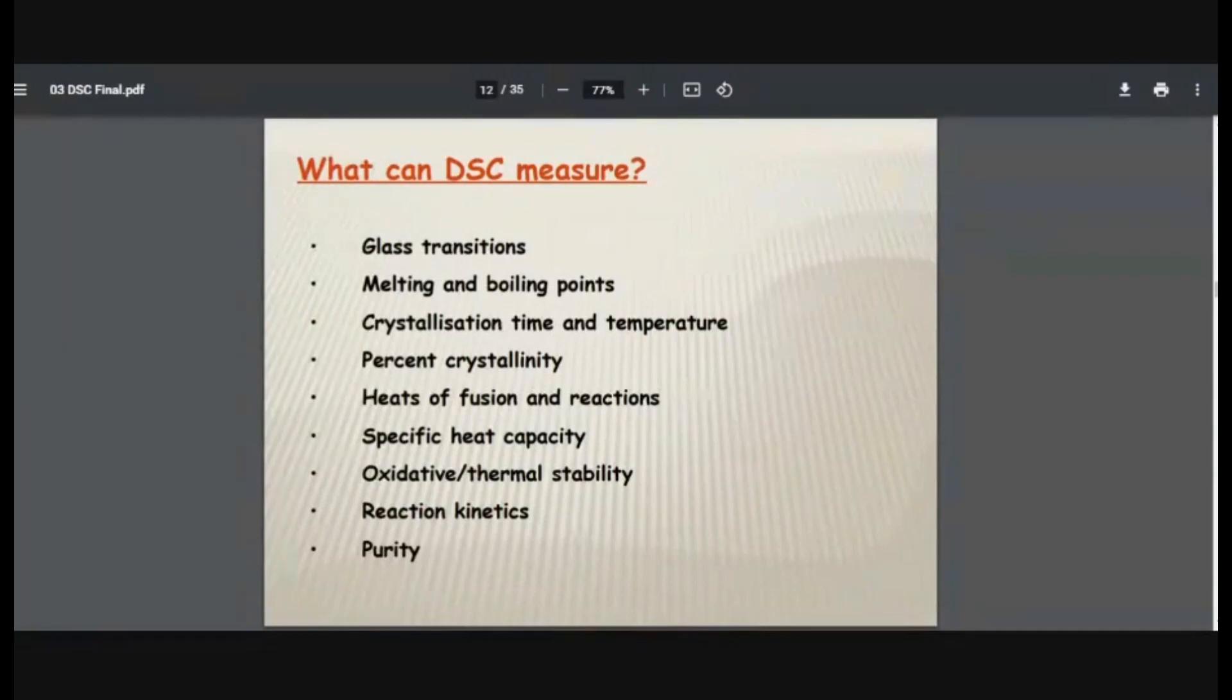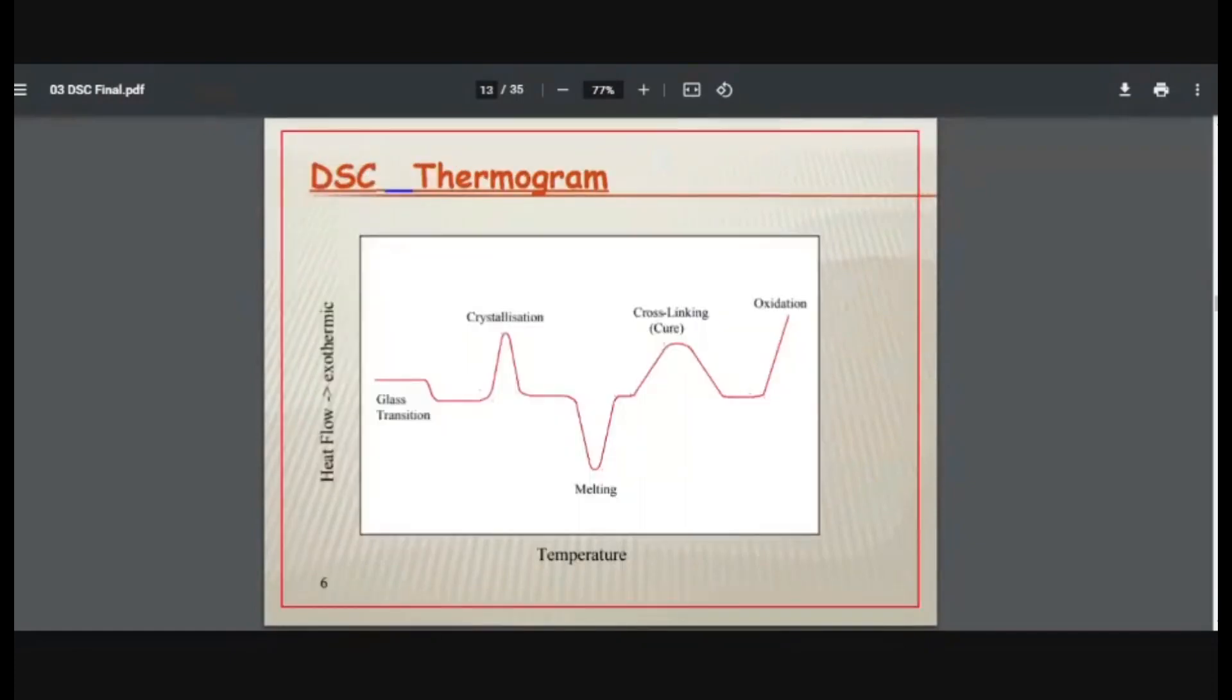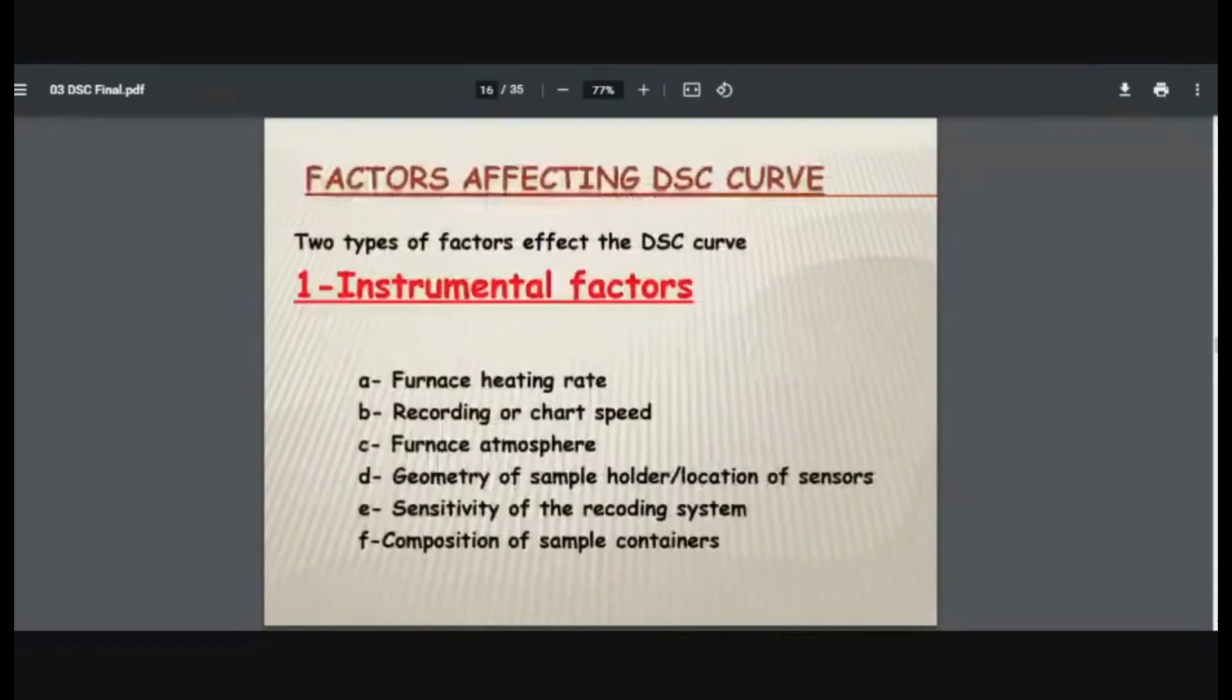Application. What can DSC measure? First, glass transition. Then melting and boiling points. Then crystallization time and crystallization temperature. Percent crystallinity. Heat of fusion and reaction. Specific heat capacity. Oxidative and thermal stability. Reaction kinetics - that is rate of reaction, time of reaction, all that. And purity. So a typical DSC thermogram looks like this. If it is a glass transition, it is a slight decrease in the temperature, or you can say endothermic process. Then for crystallization, when crystallization happens, exothermic reaction - sharp. Then for melting again, endothermic. If there is cross-linking polymer changes, it is again exothermic. And oxidation again, exothermic. Let us not go in this deep.